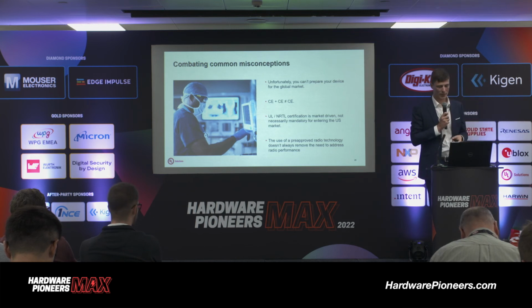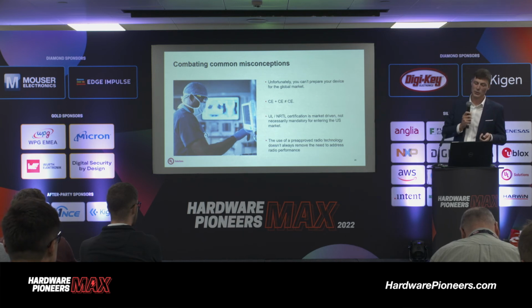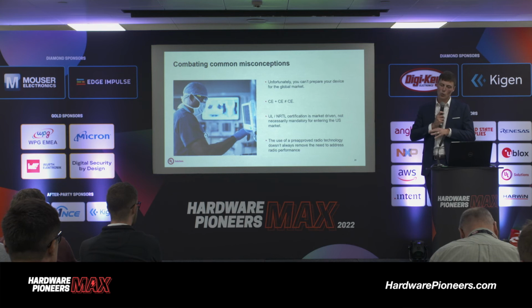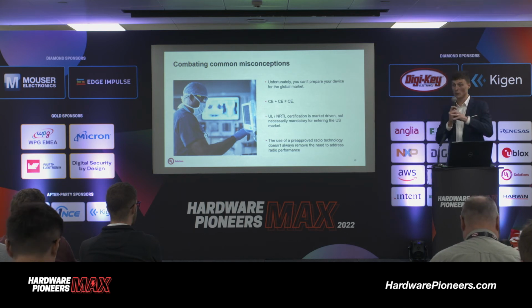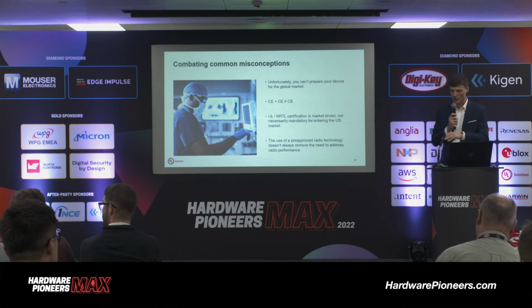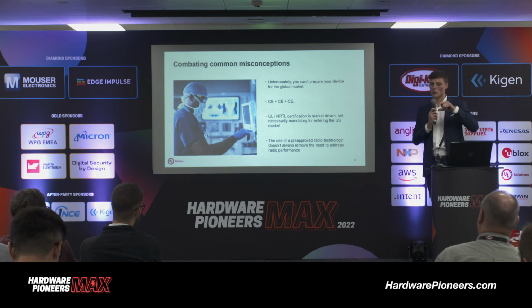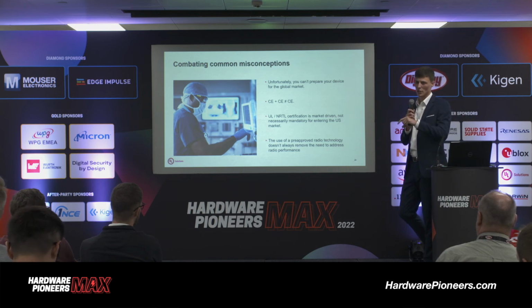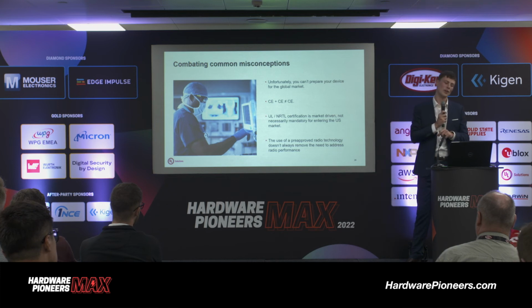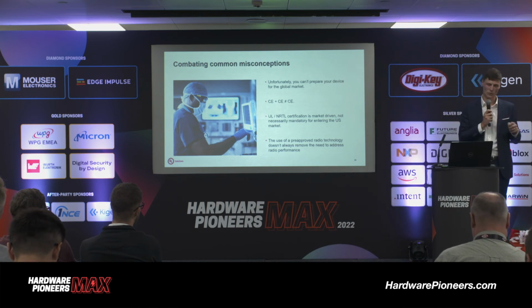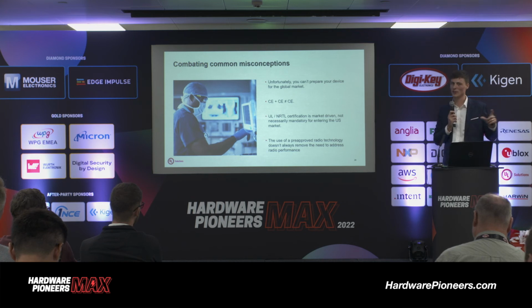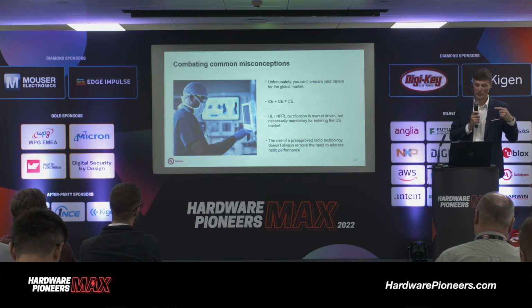And then finally, in terms of common misconceptions I've seen, the use of a pre-approved radio technology doesn't always completely remove the need for you to look at the radio performance of your device. So it does a lot of the heavy lifting, but say for example you installed the module in a way that wasn't determined in the grant conditions of its certification, or you attach an external antenna which wasn't listed in terms of the external antennas that the original module manufacturer said you needed to use. These are instances where we're not saying you need to redo every activity, but it would be prudent to consider doing some limited testing to make sure that that radio performance has been maintained.